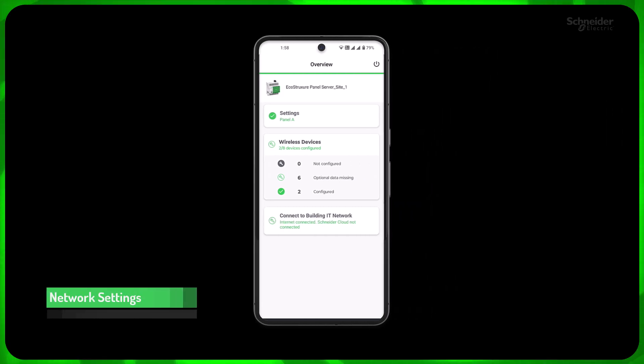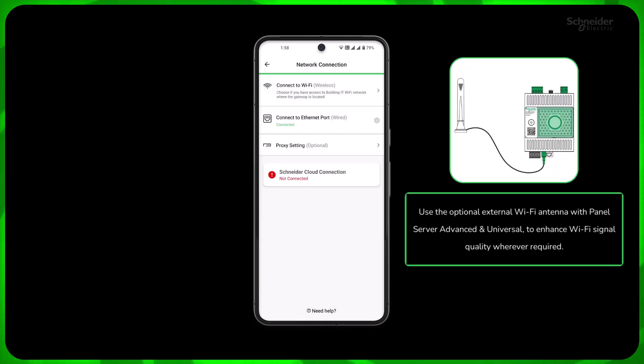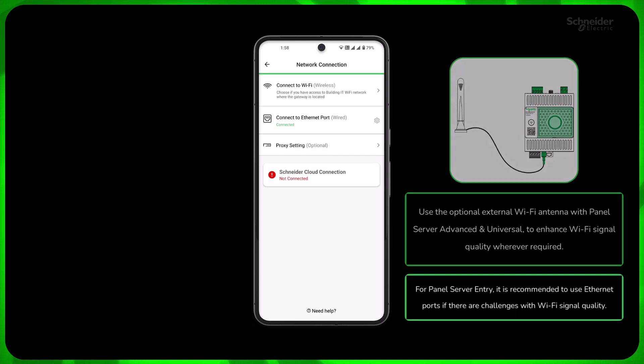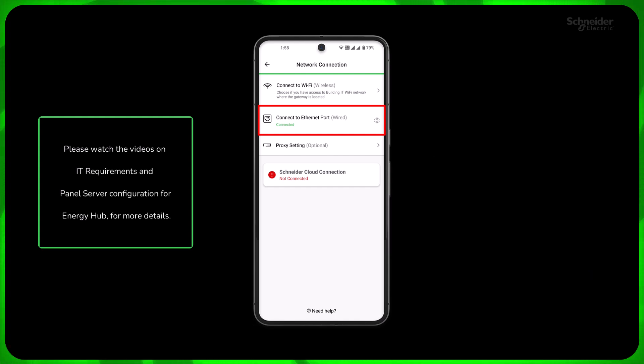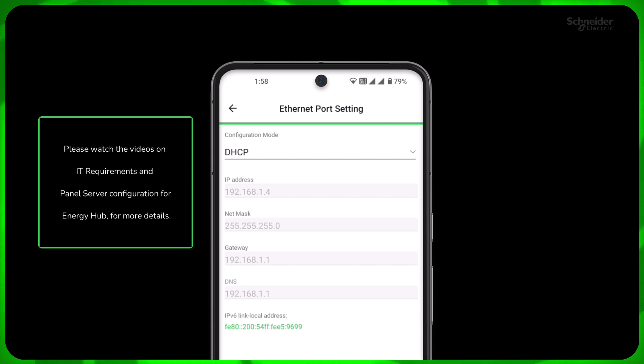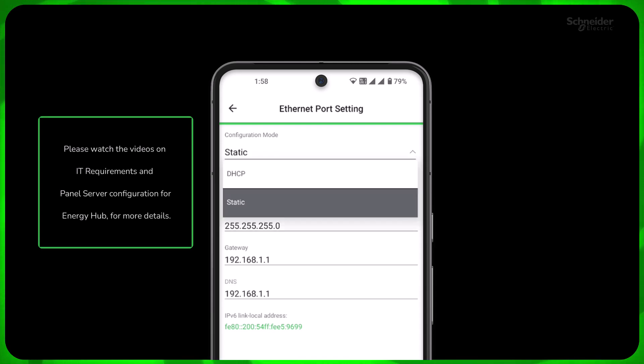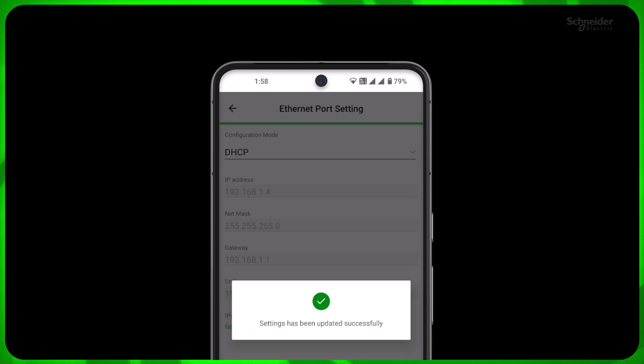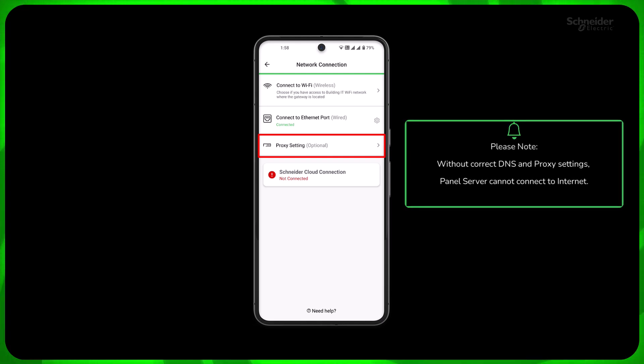Now let's configure the network settings of Panel Server so that it can access internet and connect to Schneider. Click Connect to Building IT Network. Panel Server can access internet either through the client Wi-Fi infrastructure at site or through wired LAN connected to its Ethernet ports. If you are connecting through wired network, click Connect to Ethernet port to configure. You can set the IP, gateway settings and DNS to DHCP so that your router automatically assigns these, or set to static if your IT administrator provided the details. Click Apply. Also make sure to set the proxy settings and port if your network uses a proxy server to access the internet. Without correct DNS and proxy settings, Panel Server cannot connect to internet.